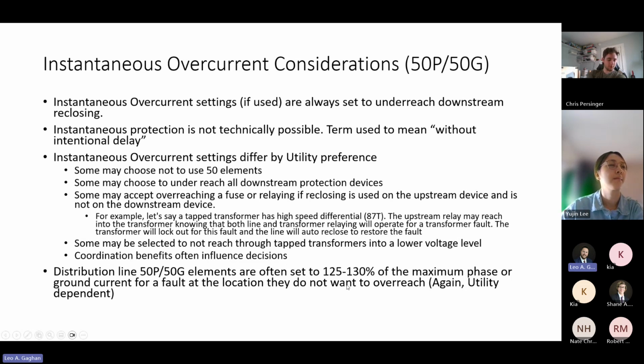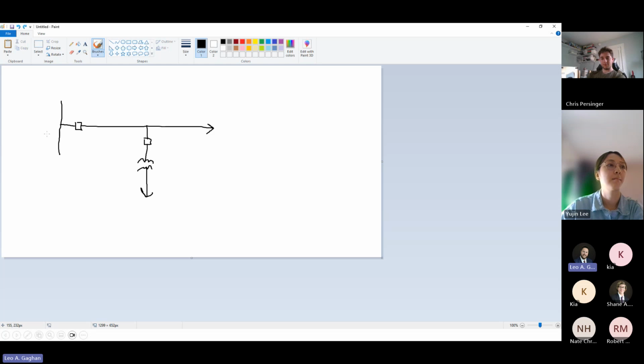And then a typical setting of that would be 125 to 130% of the maximum phase or ground current for a fault at the location they don't want to overreach. So let's say this is the location that they don't want to overreach. If a fault were to happen right there, let's say we had 5,000 amps. Well, we don't want to operate for a fault on that spot. So let's set our setting for 6,000, right? That way we won't operate for it. We'll probably operate up to here-ish, but we're not going to operate for that. So that'd be a typical approach.